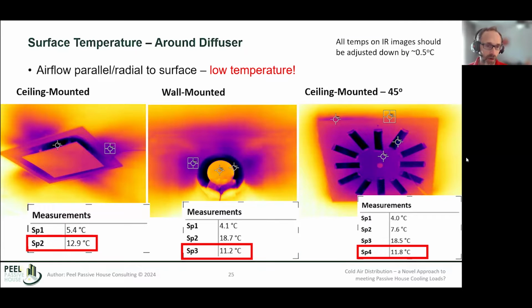In terms of surface temperature - another risk here - if we look around the diffuser, not on the diffuser itself but the drywall around it, what's the temperature there? We found that basically any diffuser sending air parallel to the surface it's installed on, radially outward, shows low temperatures. Not really surprising, but it's a nice reference to have.